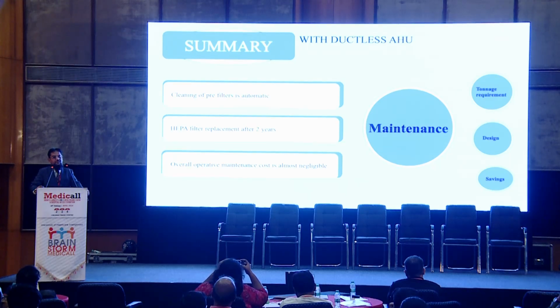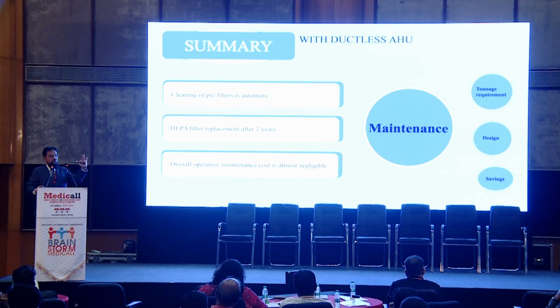From the maintenance point of view, as I said, no routine maintenance is required. What is the maintenance now? Ducts are taken care of. For the AHU, there are no pre-filters to get cleaned. The third thing, which is the most important, is the condensing unit, the outdoor unit. For the maintenance of the outdoor unit, any technician can look after it: if the gas comes down, you have to check the pressures, then clean the condensing unit. These are the routine cleanings which any AC technician does. You have to take care of that much only. No other maintenance.